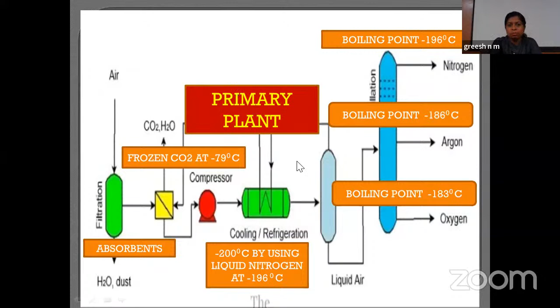From the primary plant, the oxygen will be transferred to the secondary plant. This secondary plant is usually located at a site very close to the customers. In the secondary plant, the oxygen will be stored either as liquid oxygen or as gaseous oxygen. The conversion from liquid oxygen to gaseous oxygen occurs with the help of vaporizers. From the secondary plant, the oxygen finally reaches the customers. This is how the transportation of liquid oxygen happens.